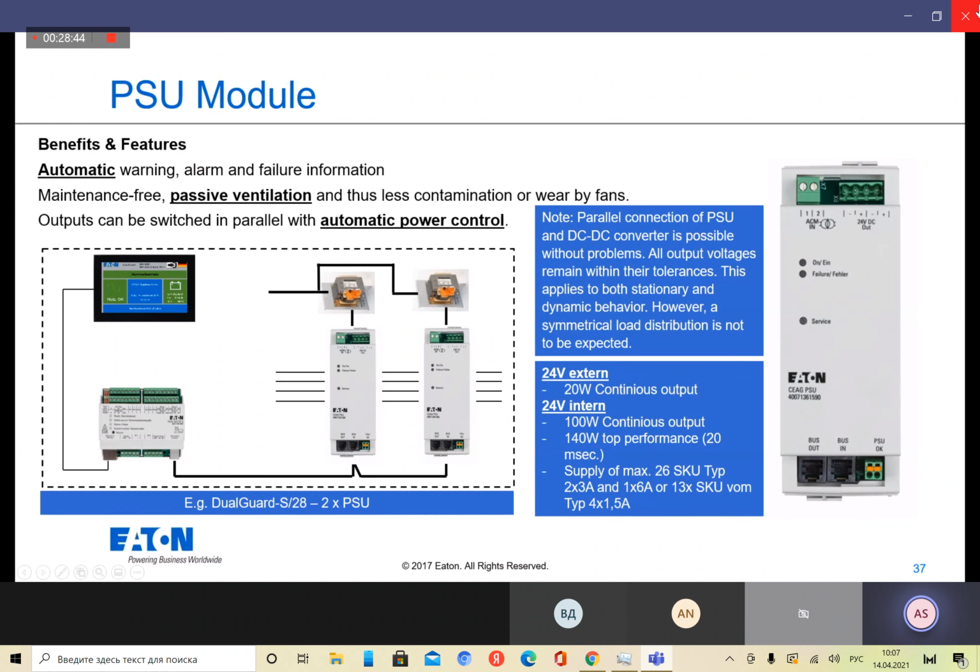Yeah, the PSU contact can be used with the combination of PSU and ZBS. Just connect this contact to a Z input. Okay. Go with 24 volts through this contact. This contact is closed when you have a failure. Okay, you can use it as an external failure on a ZBS, for example.